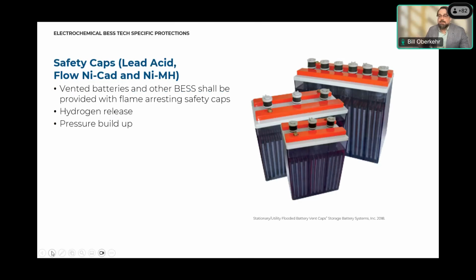Safety caps deal with gases released during normal charging and discharging operations - for instance lead acid will release hydrogen. Safety caps mitigate the buildup of that hydrogen; they release, similar to a deflagration panel. You do not need that for lithium ion batteries, because there is no buildup of that type of gas during normal charging and discharging operations.